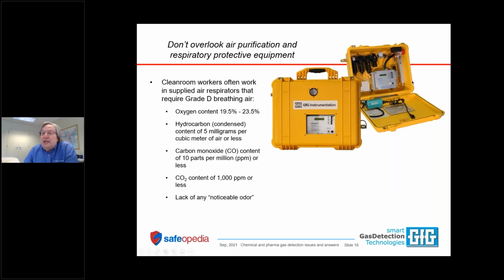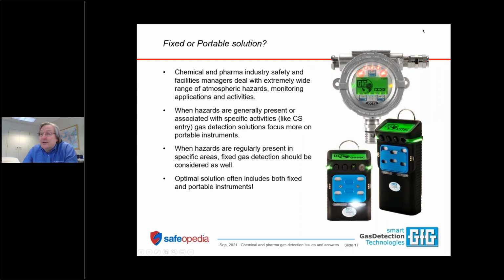Don't overlook, especially in clean room and areas where you are especially sensitive with regards to biological contamination, a lot of the time you have workers that will be working in supplied air respirators, which require a grade D breathing air source. So if you have people on supplied air respirators, do make sure that you are supplying them with grade D breathing air, and if necessary, that you have a portable or wall-mounted purification panel, and that you're monitoring that airstream for carbon monoxide and or dew point and or often oxygen as well.